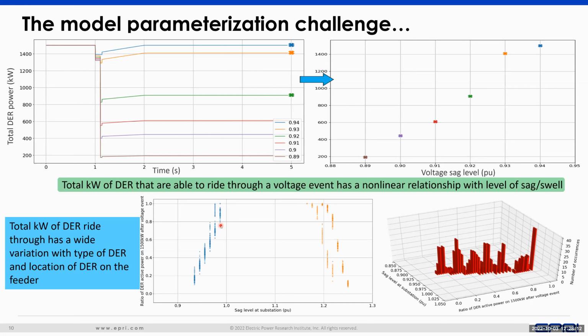So now what's shown here is if I create a set of runs which randomizes the location of DER on the feeder, then I can get a very different set of tripping that can occur. For example, here, if I have one set of locations of DER, 60% of the DER are able to ride through for this event. But if I change the locations of DER, all the while keeping the same amount of total DER coming out from the feeder, then 100% can also ride through. So fitting a linear trend for this can become difficult.